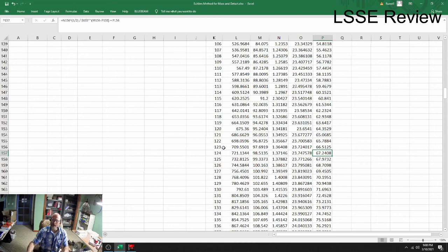So in this case, though, if I'm sizing my RTI based upon a possible fire, the flashover situation at 725 or thereabouts kilowatts, well, I've already flashed over in this particular crazy case before my detectors got off. So I'm going to look for a temperature rating that's below this.